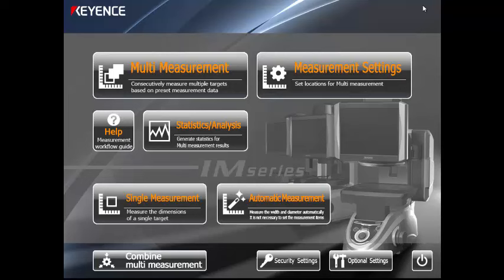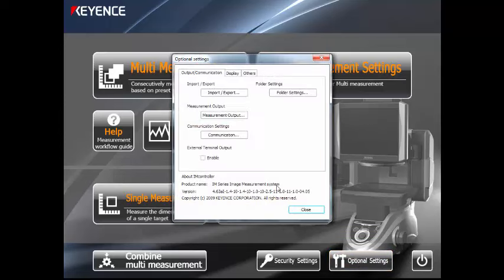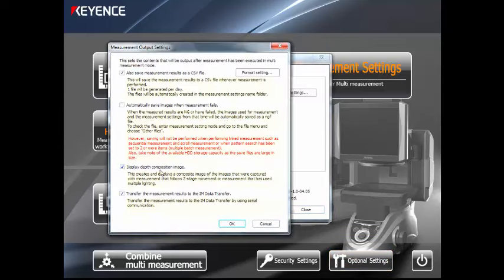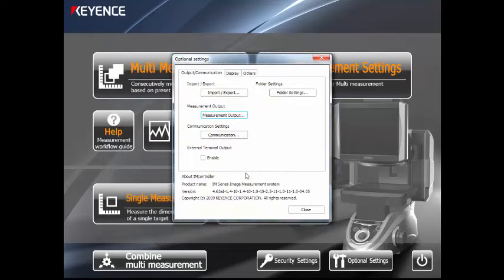Right now we're working on a fairly new system. First thing we have to do is turn on the RS-232 outputs. To do that, go to Optional Settings and then go to Measurement Output. Down here at the very bottom is Transfer the Measurement Results to the IM Data Transfer. This is essentially the serial communication. Click that and that'll turn on the capability.